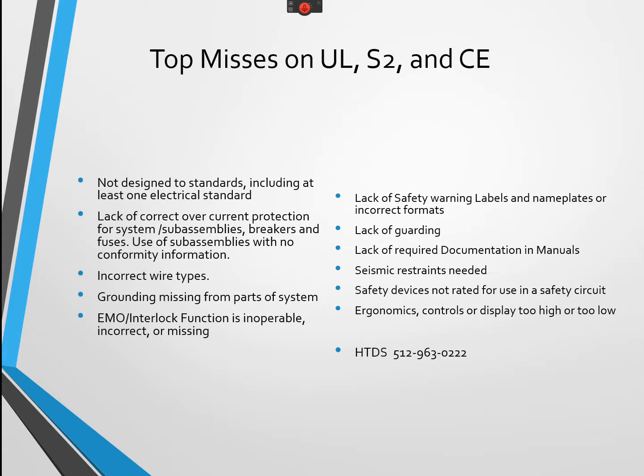Each individual ground wire needs to run to a single stud. Often you'll see it done with a terminal block, either one main terminal block where the main ground wire from the facilities comes in and grounds to the frame and to everything else, or distributed ground blocks throughout your machine, depending on how big a machine it is.